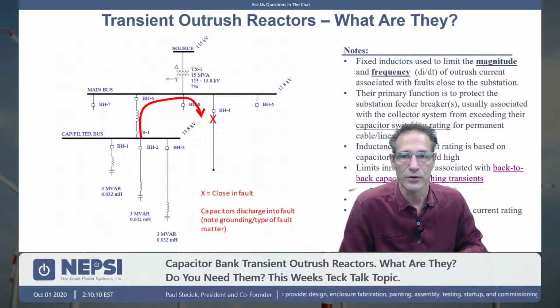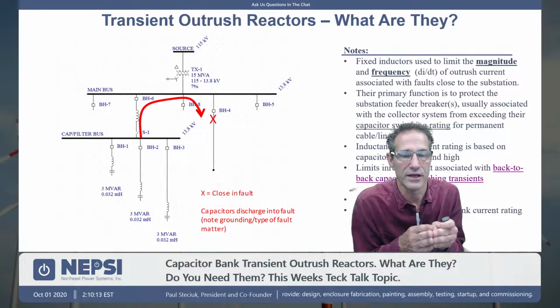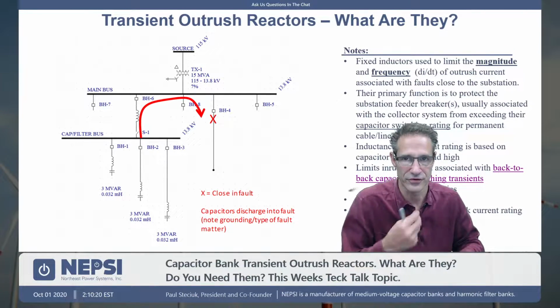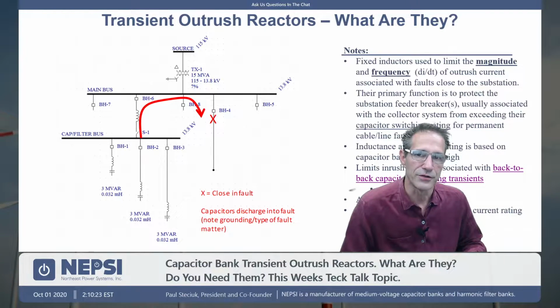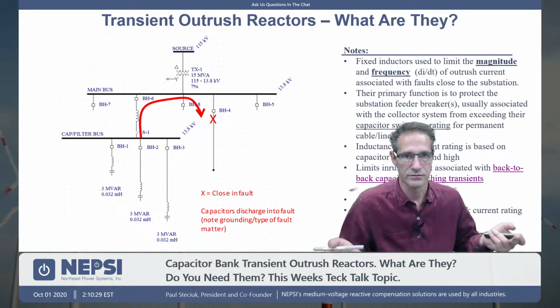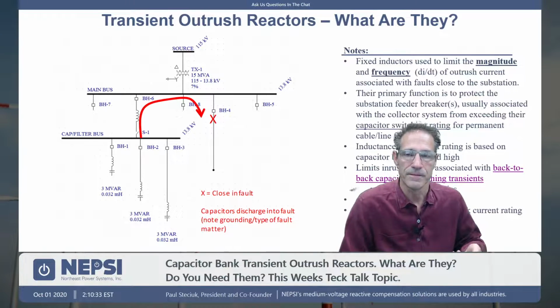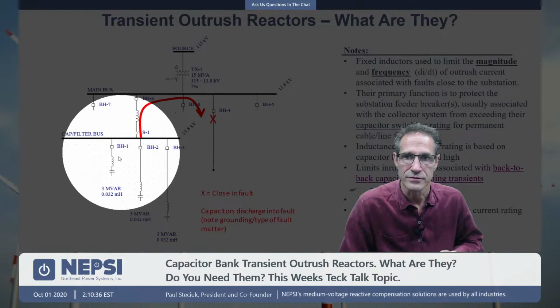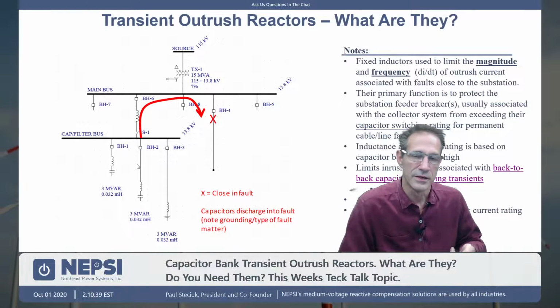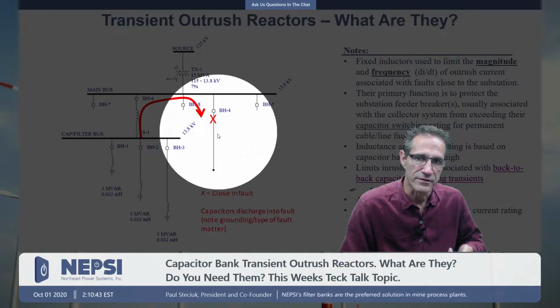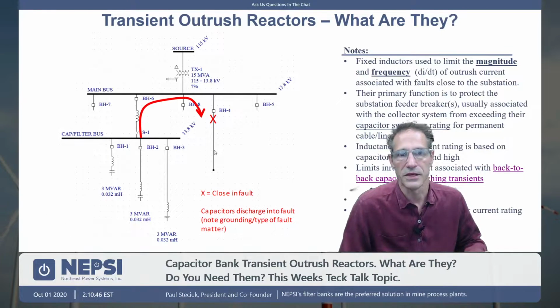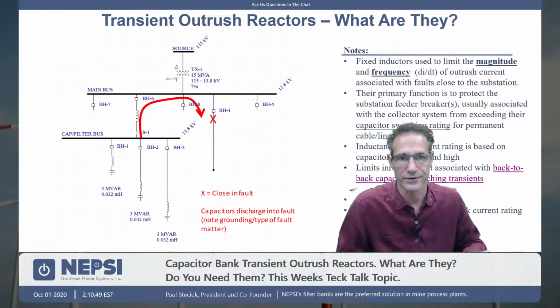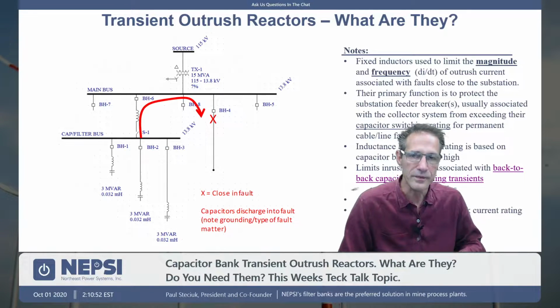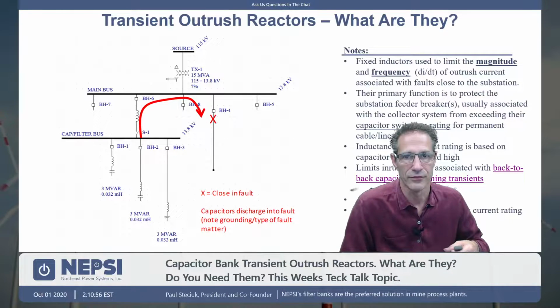What happens at that point is the breaker is closed, and the breaker can handle that high current that you would get during that fault condition, during that discharge period. No issue there. The bigger issue now is that after the fault has occurred, this breaker BH4 opens. The system is cleared. This capacitor bank would be put back into operation. It's energized. And they send some line guy out there to fix this cable or to figure out what's going on. Maybe he can't locate the fault. He blames it on lightning, which a lot of times is just a flashover event and it goes away. And he re-energizes BH4.